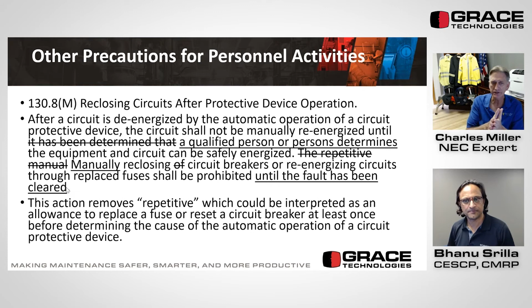All right, let's go to the next slide. This talks about how the last sentence of 130.8M was moved to the exception. It's still there, but the wording of that was really more of an exception to the main rule. It said, and this didn't change, when it's been determined from the design of the circuit and overcurrent device involved that the automatic operation of the device was caused by an overload rather than a fault condition, examination of the circuit or connected equipment shall not be required before the circuit is re-energized. So this allows it to be re-energized for conditions caused by an overload.